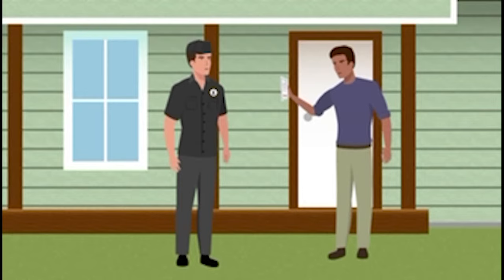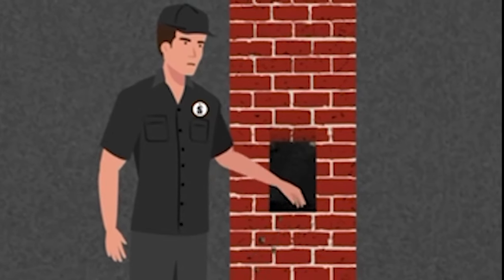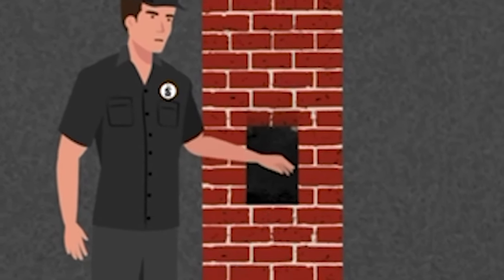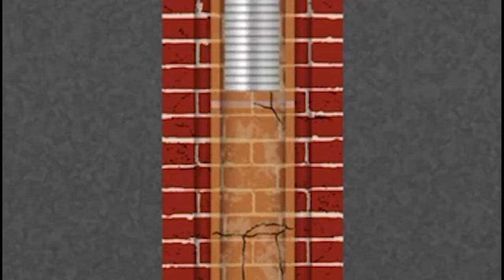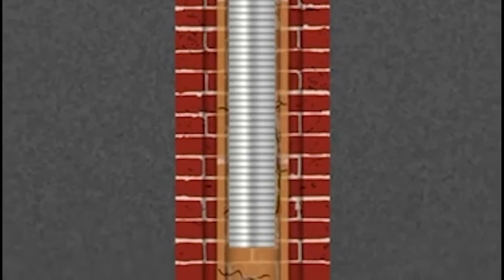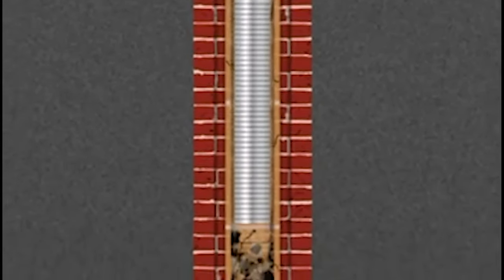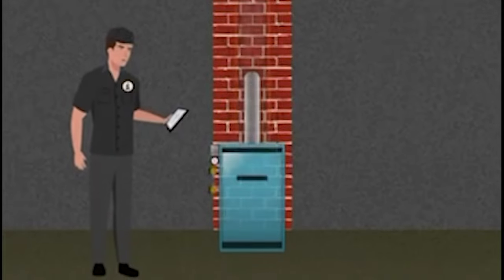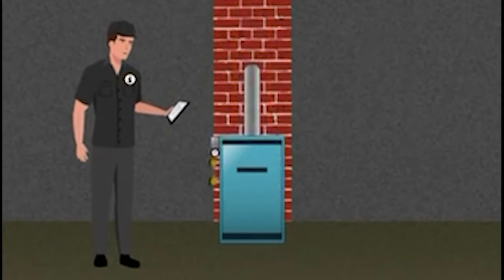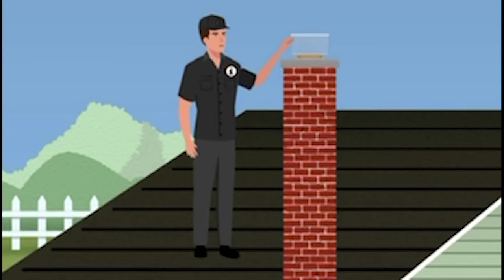Right now, we can install a stainless steel, smooth wall, UL-listed lining system from top to bottom, bypassing all the damaged sections of clay, and connect it directly to the smoke pipe coming off your heating appliances. This system creates an airtight seal from top to bottom. Also, properly sizing the lining system will ensure a consistent, safe, natural draft all year round.